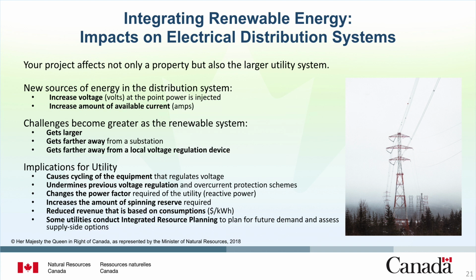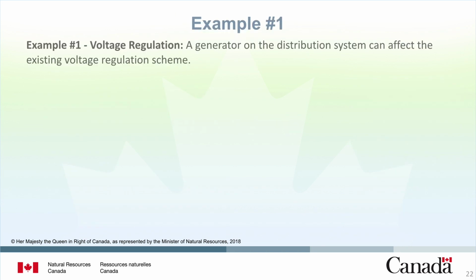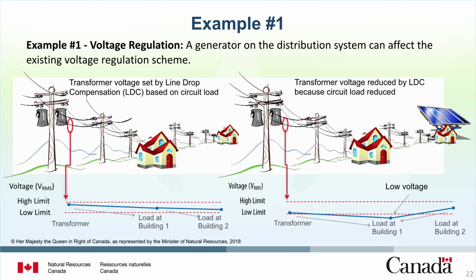Now let's walk through three examples of how a renewable energy project may impact a utility. As a first example of voltage regulation, consider that the utility must deliver power with high and low limits of voltage. Voltage drops along a power line as the load goes up, and the transformer must regulate voltage based on the load. Adding a PV generator to an energy distribution system can affect an existing voltage regulation scheme. PV generation on a circuit will reduce the load seen at the transformer and result in line drop compensation. This can push voltage to higher or lower than the imposed limits.